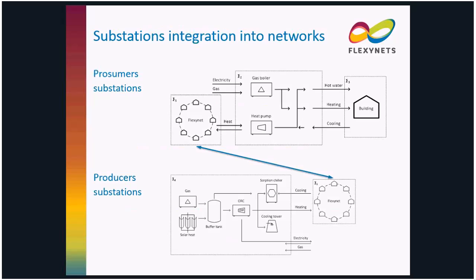And as Anna announced, since we are working at very low temperature, 10 to 25 degrees, we need some device to increase the temperature to the level needed by the building's heating system and domestic hot water preparation. So basically we have a heat pump, as you can see in the first sketch, which increases temperature from the network level to the needed one.